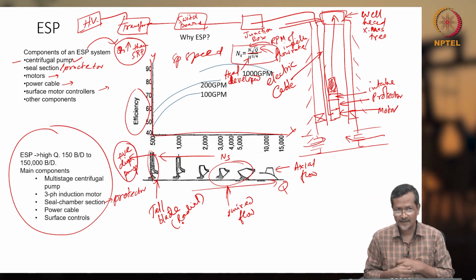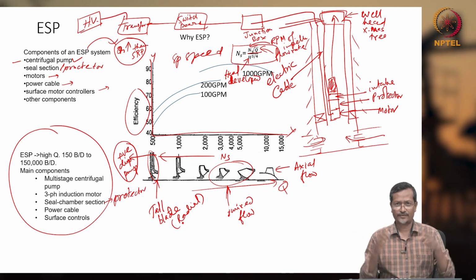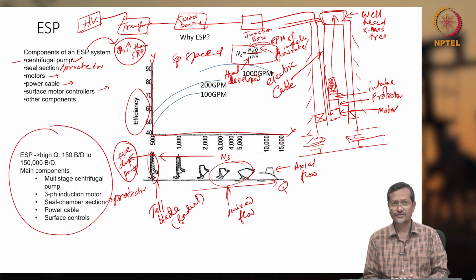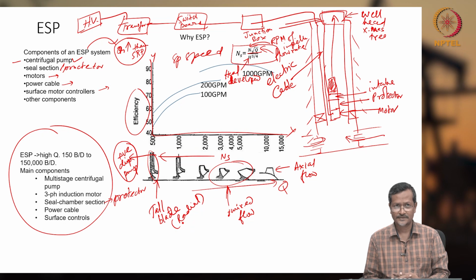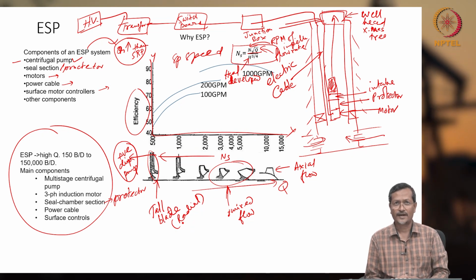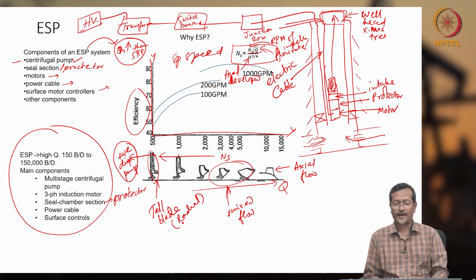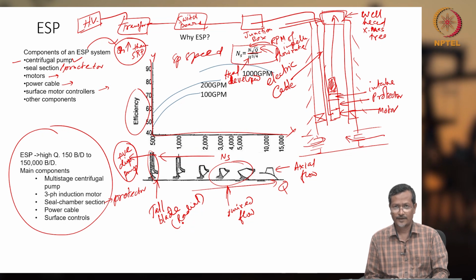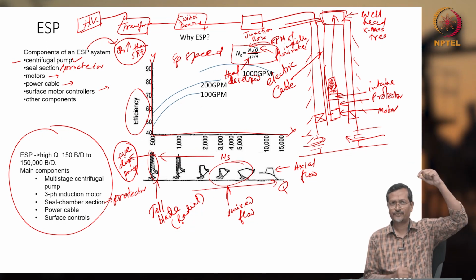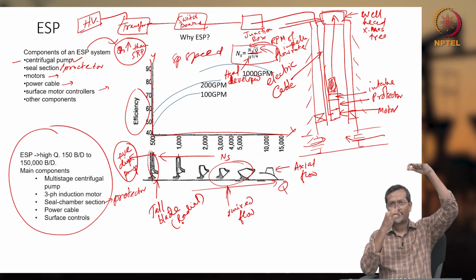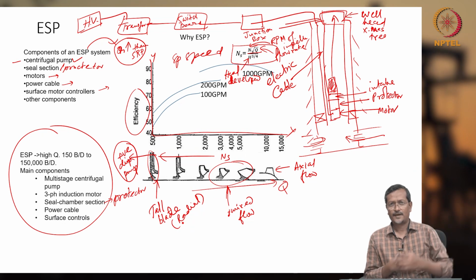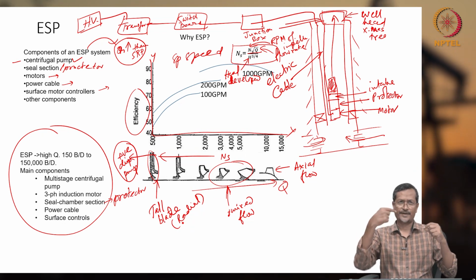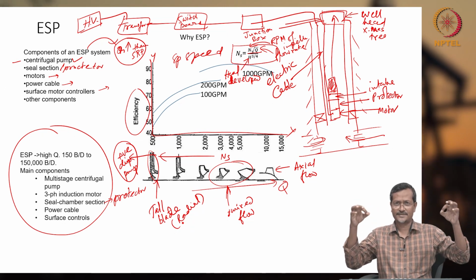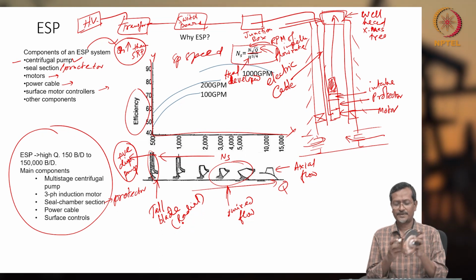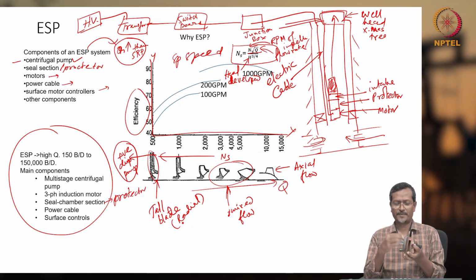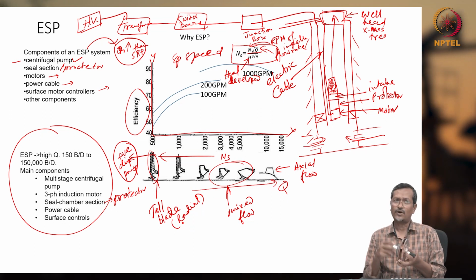And if you see the ceiling fan on the top of your head, maybe in summertime all over India you are running this ceiling fan, the ceiling fan is actually an axial flow fan. The property of an axial flow fan or axial flow turbine is that it handles a very high amount of fluid, and the head or pressure development will be very low. An axial fan delivers just a certain amount of pressure. If you take the pressure above the fan and after the fan, the difference will be maybe 0.1 bar. For a wind turbine also the pressure difference will be less than 1 bar. But if you are using a centrifugal pump, the pressure difference can be 5 bar also. Inlet pressure may be 1 bar, the exit pressure may be 5 bar, and more than that is also possible.